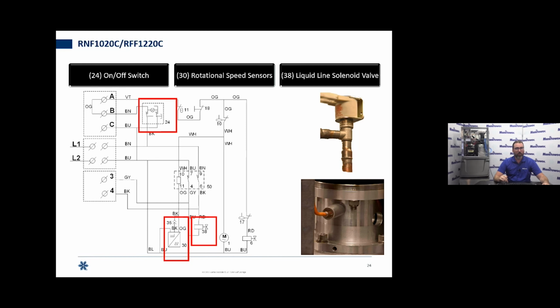But before we ever open up that liquid line solenoid coil, we need to establish rotation. So in place of the motor contactor coil, here we're using it to control the relay that's controlling the liquid line solenoid. Same operation, same troubleshooting steps apply to this, same color LED. Everything is the same other than what we're actually controlling changes from the motor contactor coil to the liquid line solenoid relay coil.